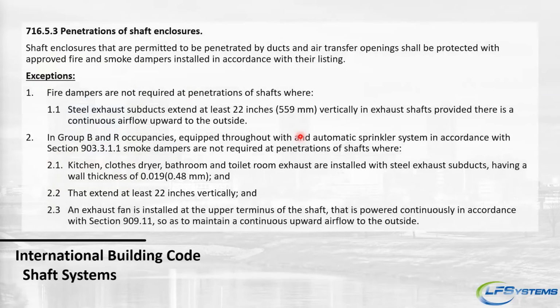When it comes to shafts, we talked about how you cannot have dampers in a dryer exhaust system, but if you look at the IBC, any fire rated duct that's penetrated must have a fire smoke damper. So how do you get around that? Well, the exceptions to the fire and smoke damper is an exhaust subduct extending 22 inches vertical into the shaft. So we call it the subduct method. Instead of having a fire smoke damper on the inlet of that shaft, we'll put a steel subduct into the shaft and extend that 22 inches.